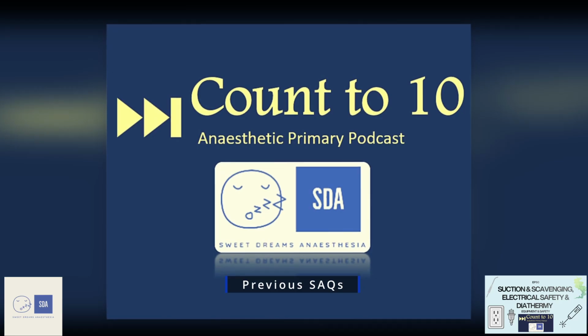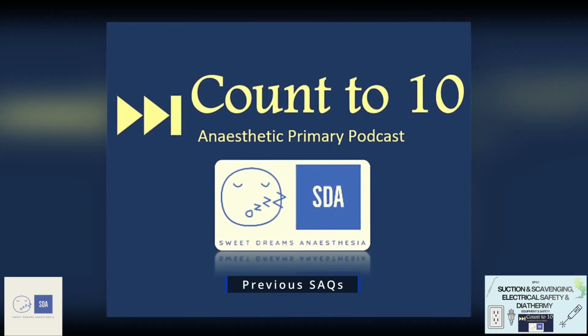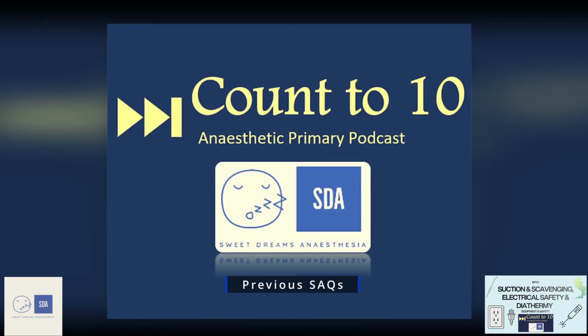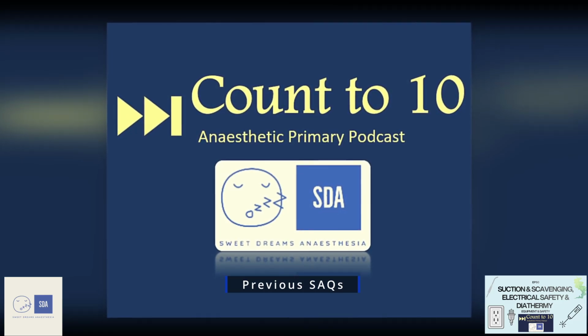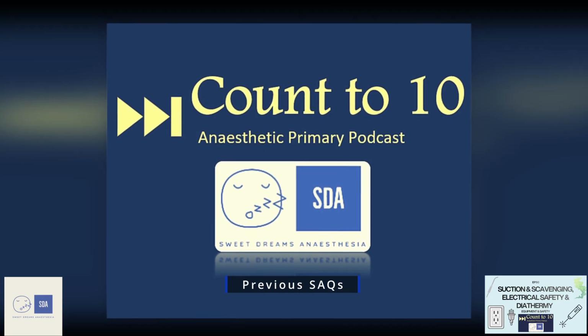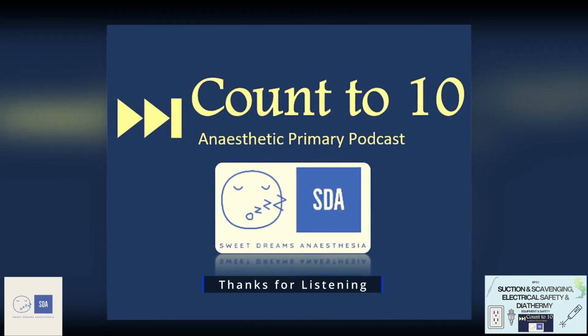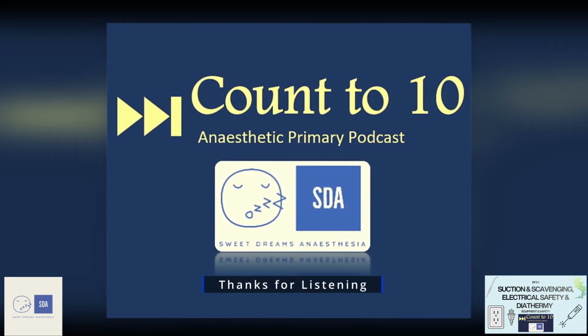In terms of hazards, you can break this down into electrical burns, electrical interference, tissue damage, and diathermy smoke. And with this, never forget the 3 things you need for an electrical fire. You need some combustible substance, an oxidizing agent, and then an ignition source. And the ignition source can be either diathermy, laser, or anything that's electrical.